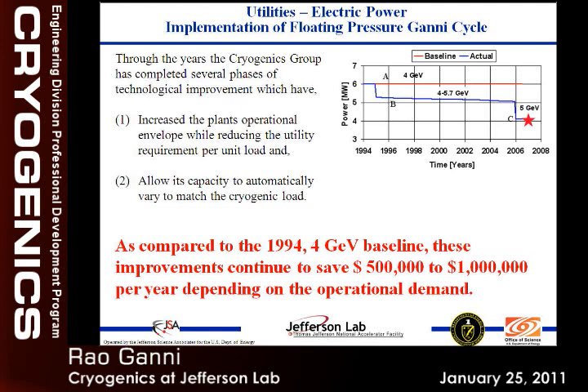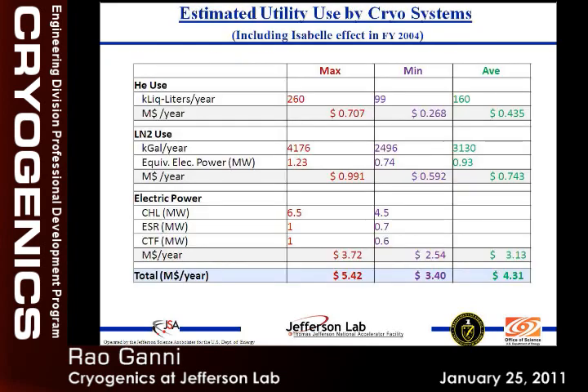This is the floating pressure Ganni cycle. We used to run at 6 megawatts constant whether we needed it or not. Then we started allowing the plant to float, and now at the 4 GeV level we only use 4.2 megawatts instead of 6 megawatts — that saves more than half a million dollars a year in electric power, plus additional savings in spare parts because we're not pushing the compressors. There's nothing to lose by not pushing the plant to its peak when we don't need it. We lose a maximum of about 260,000 liquid liters per year, or a minimum of 100,000. On average we lose around 160,000 per year — one and a half times our inventory.